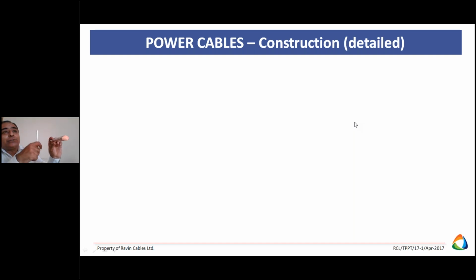Now coming to the design part: skin effect. Everybody knows skin effect and proximity effects - current flows from the surface of the conductor. Suppose we use one single strand of big diameter, the current rating will be lesser compared to a stranded conductor. We also keep mutual inductance and mutual capacitance in mind when designing. We break these rods into wires and make a conductor - one benefit is flexibility, and second is optimum utilization of material, giving more area so more current can flow.